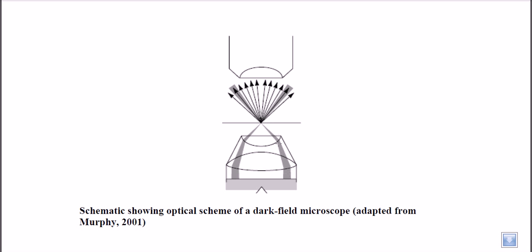Looking at this picture, think of this as the condenser. The only difference for dark field microscopy is that we place a filter here — not actually a filter but a blocker or stopper, a light stopper. It is a disk-like structure which stops the light coming directly through the center, and only allows light from the surrounding terminal regions to pass through. This peripheral light then goes on to illuminate the specimen.